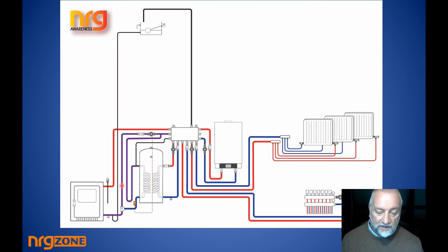an immersion, by the solar or whatever, is not going to be drifting back out and drifting off up and being lost in the house, which is a colossal waste of energy in the vast amount of installations that there's utterly no need for. So this heat lock loop dropping down below the cylinder and rising back up goes into the coil. Now it meets the cooler water in the cylinder. The heated water in the coil is cooled, it becomes more dense, it falls down, and it falls down into the center of this injector T right down here.